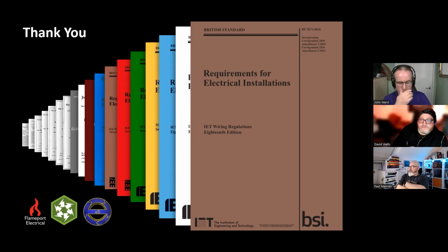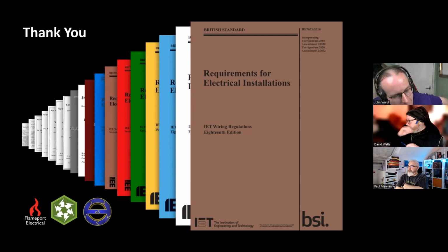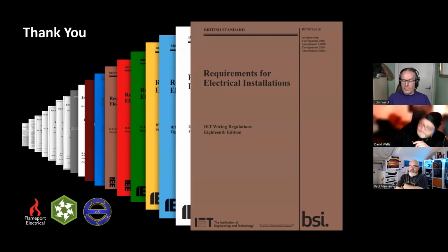Unearthing a TN system, putting an electrode in, how practical are services in the ground and getting them 5 to 10 meters away? Yeah, good question, Mr. Ryan. I'll cover this one. Okay. On a TN system, it's absolutely fine, because you're connecting an additional electrode to the combined neutral and earth conductor. The distance of about 5 to 10 meters is if you're going to use it as a TT installation. And that's when you do need to make sure it's completely separated from your TN arrangement.